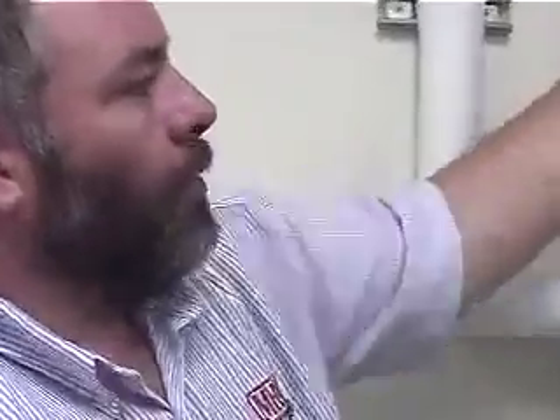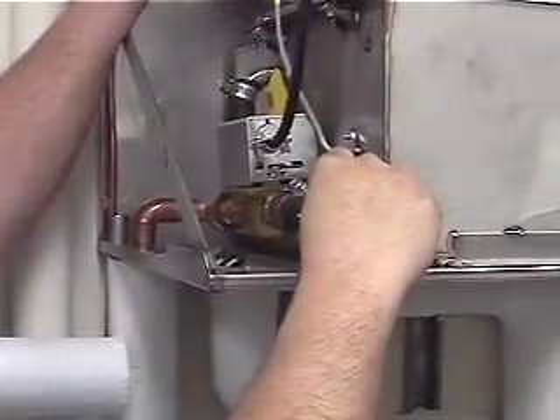So don't forget when you're popping this open, I recommend once a year we need to take these 4 bolts out of the box. There's 2 on this side, 2 on this side, the whole top lifts off. Every year we need to open this up, we need to clean it, but not only do we need to clean the bottom of this, you need to remember to clean your drain lines. Your drain lines are going to plug up, and when they do, just because you've got nothing in the pan, we're going to have problems, okay?